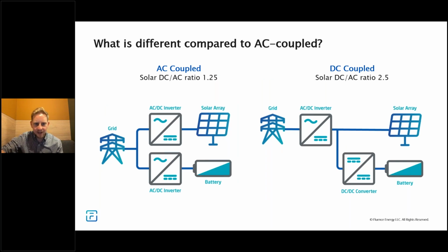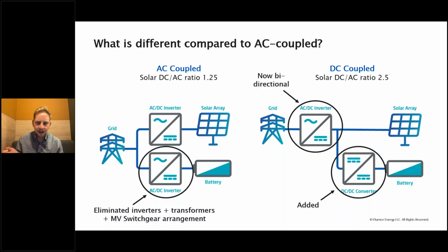To illustrate that simply, there are also benefits to DC coupled storage from a balance of plant perspective. Rather than needing a separate inverter for batteries and a separate one for solar, as you would with two independent assets, a DC coupled system only needs one set of inverters. So you save on buying two sets of inverters, transformers, and switchgear.